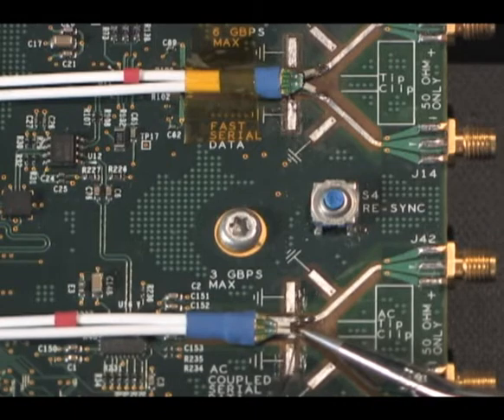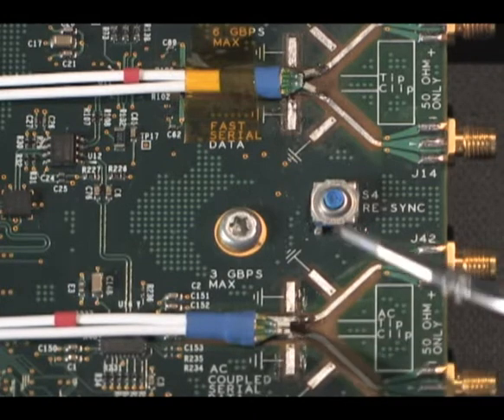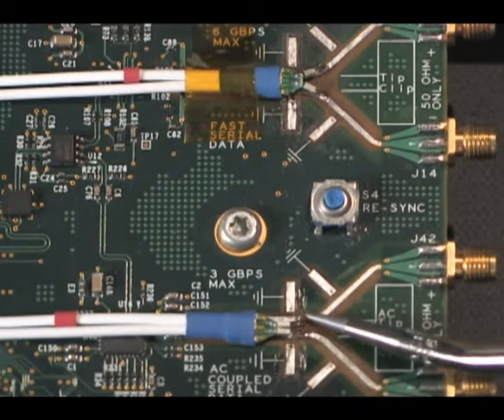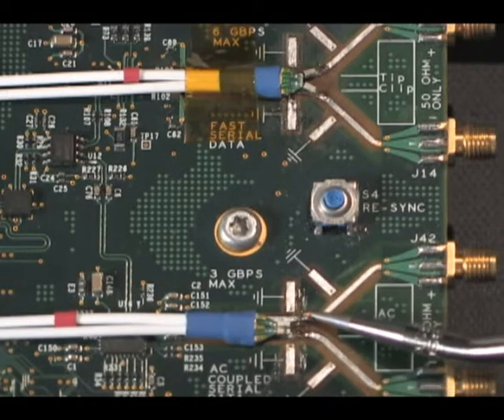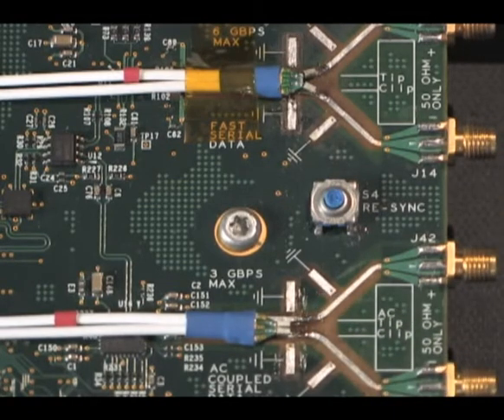Shorter wires yield better signal fidelity, but it becomes impossible to attach the probe to the device if the wires are too short. Knowing the spacing of the connection on the device and if multiple probe tips will be needed will help plan your approach. Tektronix provides many probe tip accessories to meet the needs of most every application.